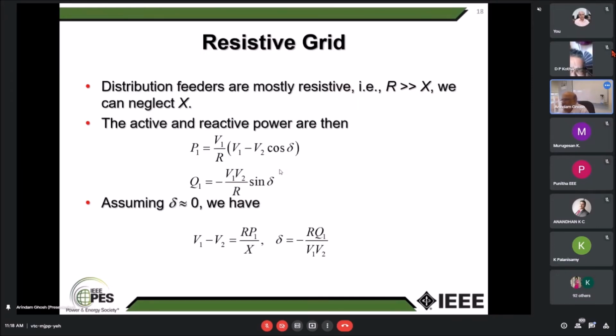Now suppose I have a resistive grid. What does that mean? Usually if you look at power transmission systems, the grids are inductive because in modern high voltage transmission systems, the resistance is almost negligible, so the grids are inductive, and you neglect the resistance. But for power distribution systems, resistances are quite high, so much so that you can actually neglect the inductance or reactance. Sometimes they might be 1 to 1, so basically you cannot assume the grids are inductive.